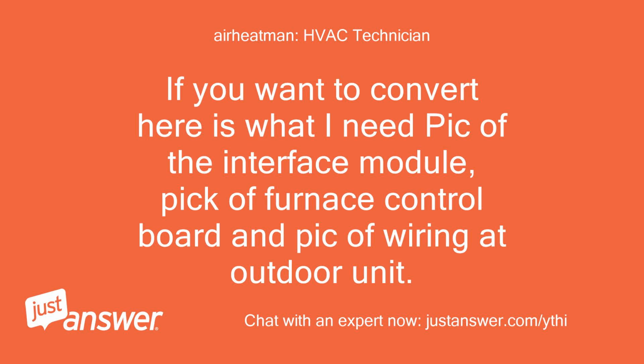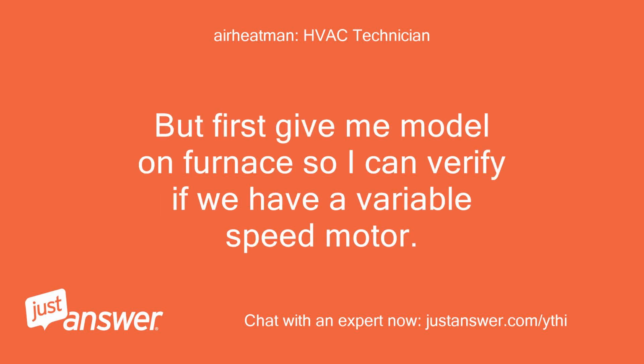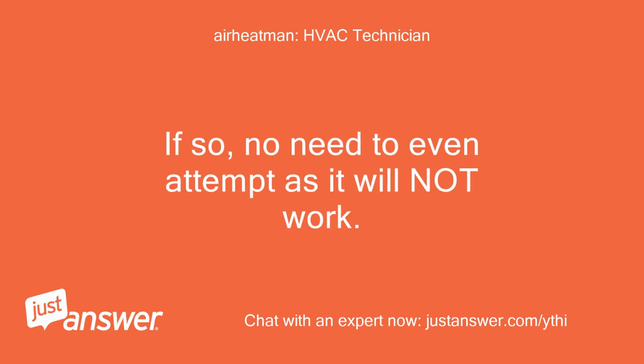If you want to convert, here is what I need: a pic of the interface module, a pic of the furnace control board and a pic of the wiring at the outdoor unit. But first give me the model on the furnace so I can verify if we have a variable speed motor. If so, no need to even attempt as it will not work.